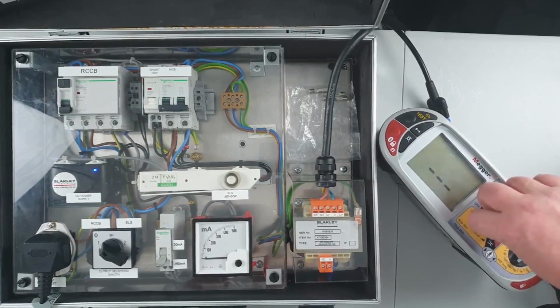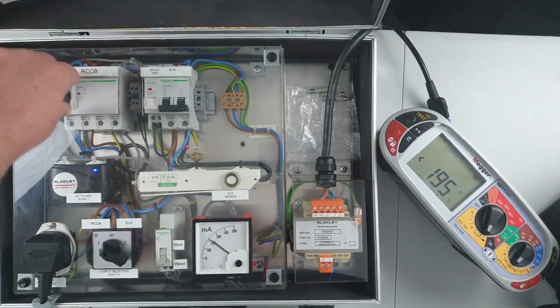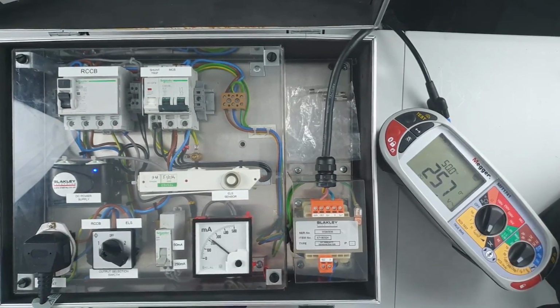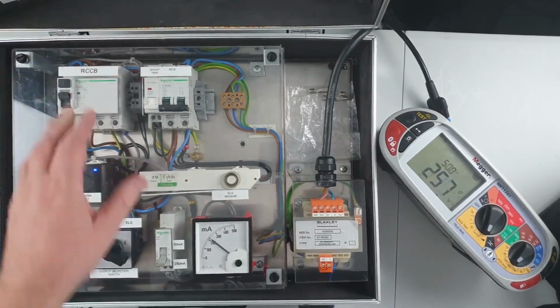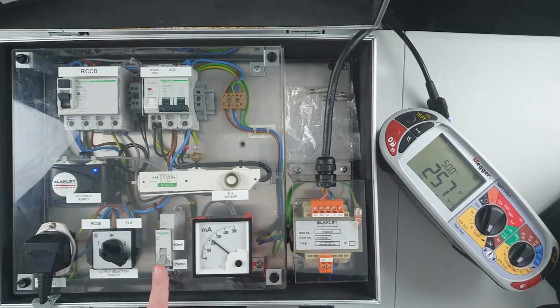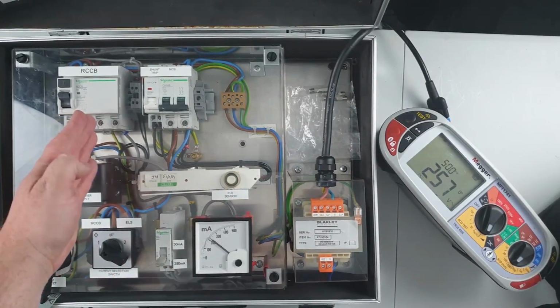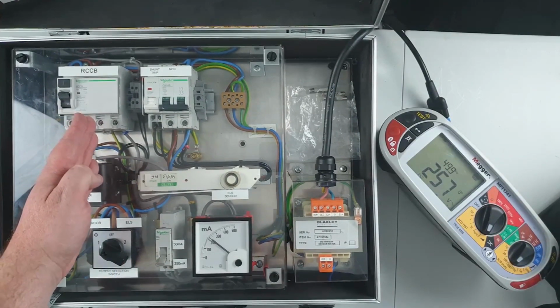If we do the ramp test on that, this 30 milliamp device is now requiring 195 milliamps to trip. That's well off. This is making this device pretty much unusable. When we have leakage of DC nature coming into the system, as we've shown in the previous video, it can really offset the device by saturating the AC RCD.